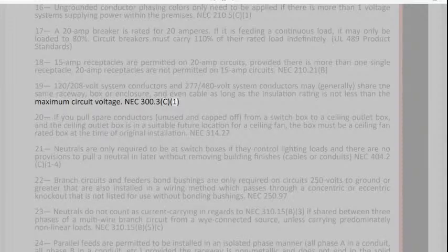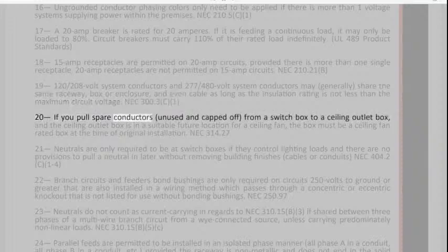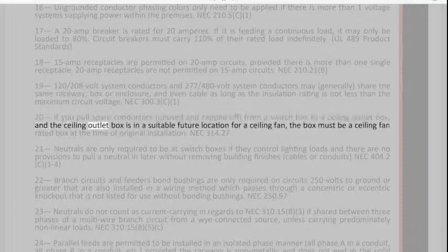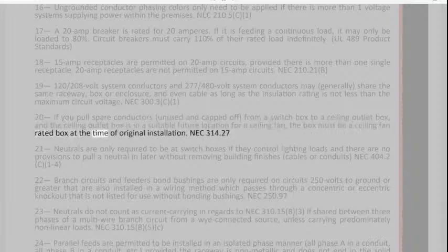300.3 C1. 20. If you pull spare conductors, unused and capped off, from a switch box to a ceiling outlet box, and the ceiling outlet box is in a suitable future location for a ceiling fan, the box must be a ceiling fan rated box at the time of original installation. NEC 314.27.